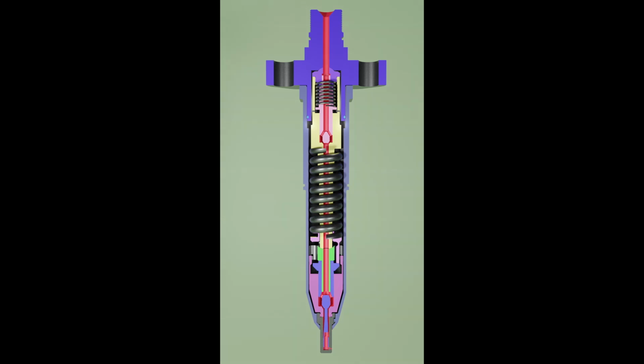As the fuel injection finishes, you can see that the cutoff slide drops back on the seat due to the spring pressure, and as the pressure further drops, the vent slide seats back on the body, uncovering the recirculation hole.